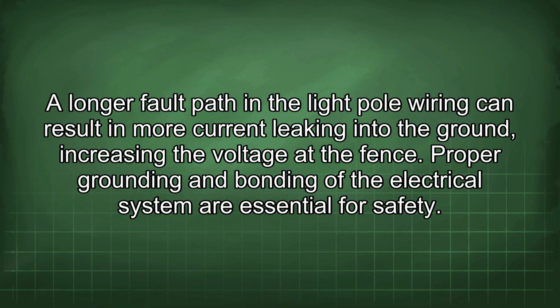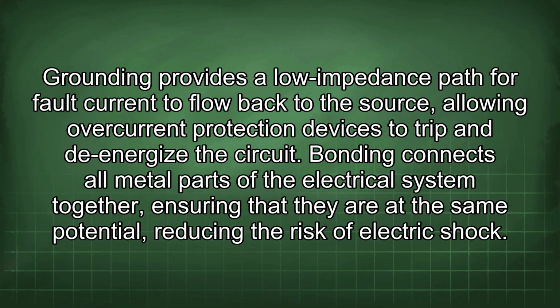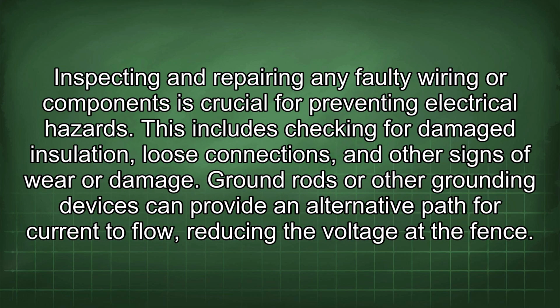Proper grounding and bonding of the electrical system are essential for safety. Grounding provides a low impedance path for fault current to flow back to the source, allowing overcurrent protection devices to trip and de-energize the circuit. Bonding connects all metal parts of the electrical system together, ensuring that they are at the same potential, reducing the risk of electric shock. Inspecting and repairing any faulty wiring or components is crucial for preventing electrical hazards. This includes checking for damaged insulation, loose connections, and other signs of wear or damage.